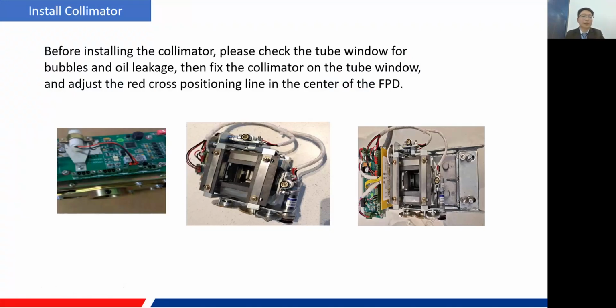Next one is the collimator. Before installing the collimator, we need to check the tube window for bubbles and oil leakage, and then fix the collimator on the tube window and adjust the red cross positioning line to the center of the flat panel detector.